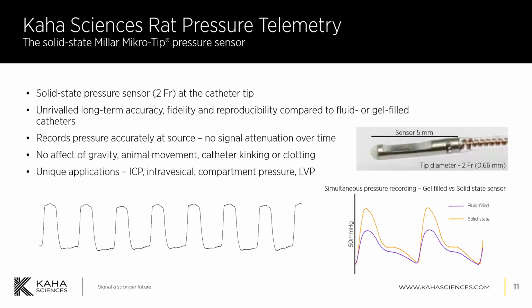And what's so great about our pressure telemetry system for rats is our incorporation of the Millar Mikro-Tip pressure sensor. This is a solid state pressure sensor which is located at the catheter tip. It's 2 French on the catheter scale, so 0.6 millimeters in diameter, roughly 5 millimeters long. And what this means is that we offer unrivaled long-term accuracy, fidelity, and reproducibility compared to fluid or gel-filled catheters. With the sensor being right down at the catheter tip, what this means is that with our telemeters, you're recording pressure accurately at source. So you're recording the pressure within the artery.